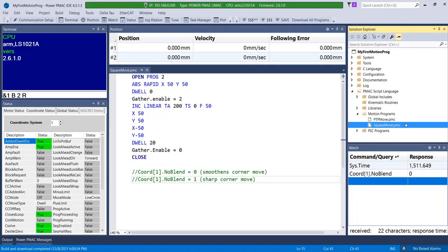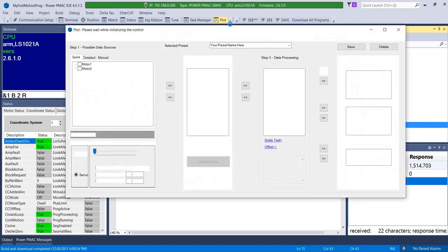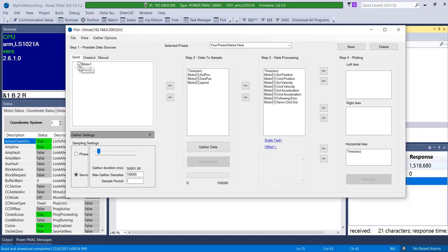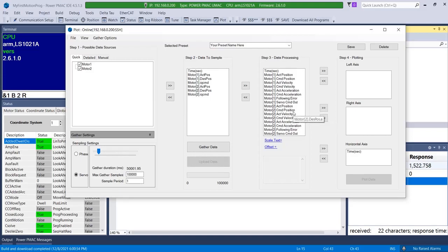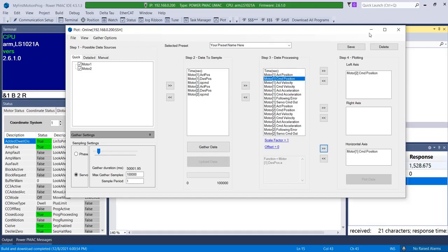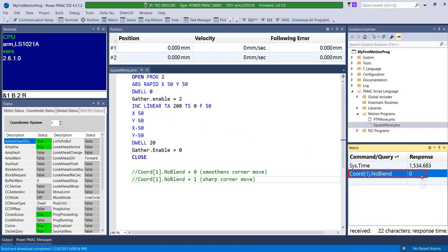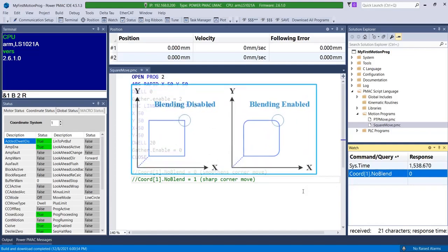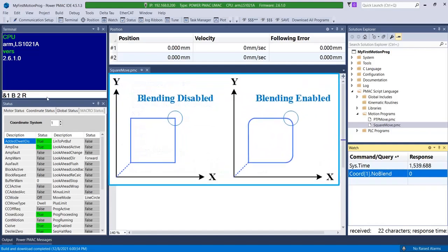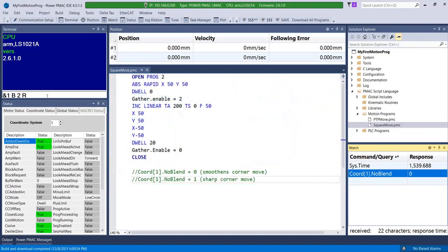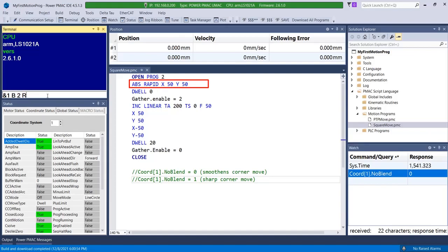With my square program already downloaded to PMAC, I'm going to set up the plot tool to view the output of my program. As per my axis assignments, motor 2's commanded position will be on the vertical axis as it represents the y-direction, and motor 1's commanded position will be on the horizontal axis as it represents the x-direction. Using what we've learned from earlier, let's draw a square with Coord[1].NoBlend equals 0. This is the default value for the parameter that enables blending. The corners of our square will now be smoothened out with an archetype of motion that blends the end of one move into the beginning of the next move. The program consists of a few linear moves. The first command moves the motor to an absolute location of 50,50 in the x and y space.